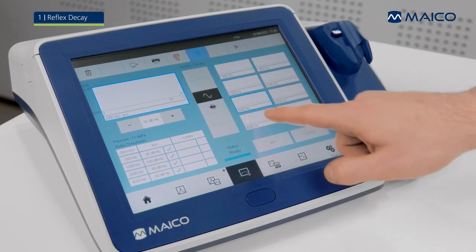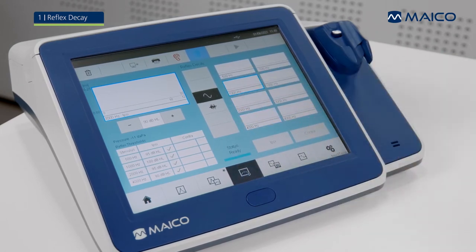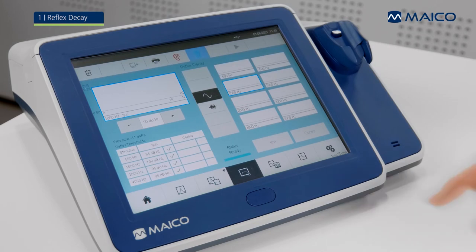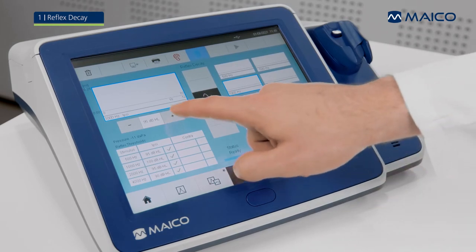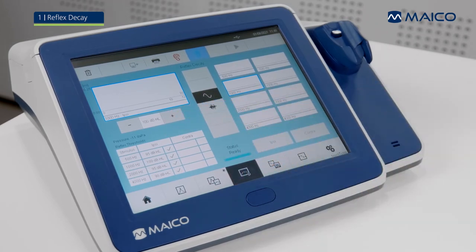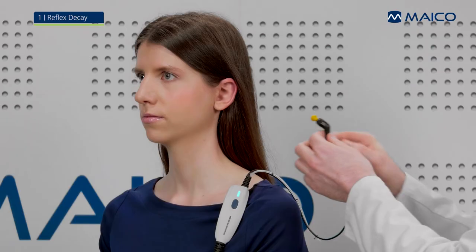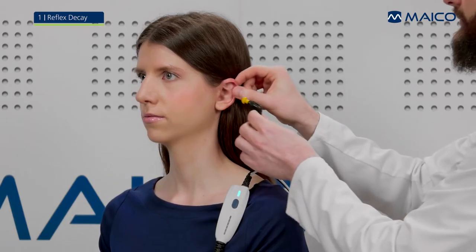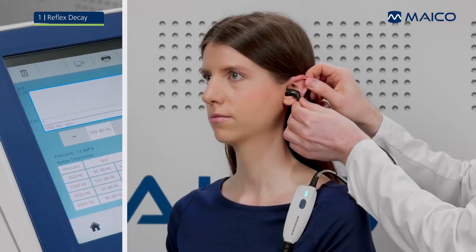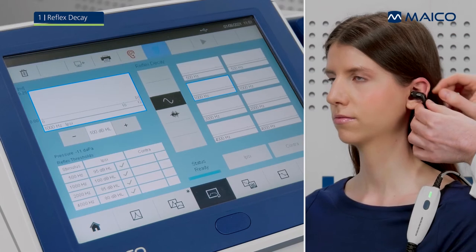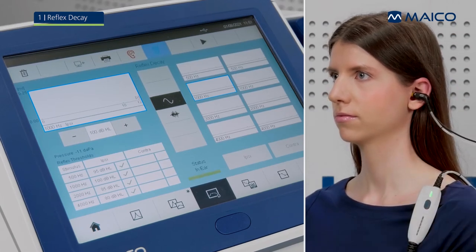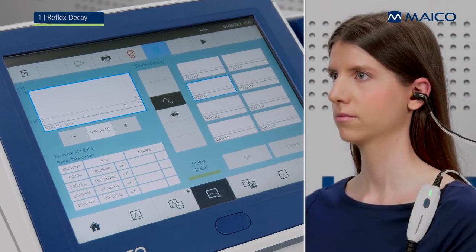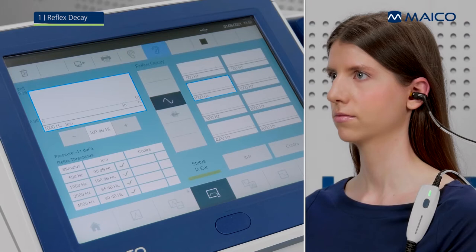Select the stimulus frequency by pressing the small box on the right. Press the minus and plus to change the presentation level of the stimulus selected. Manual presentation is required within reflex decay measurements. Press the play button or the probe button to start the measurement.